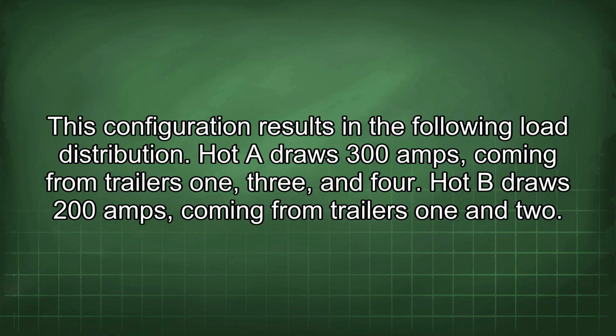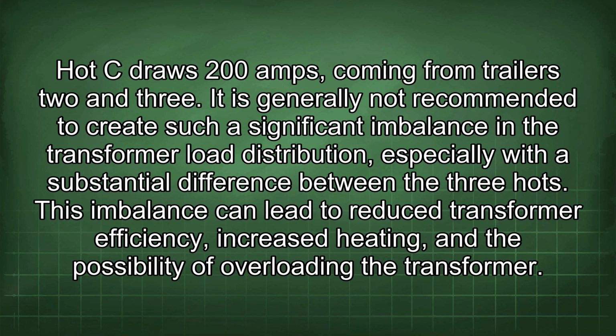This configuration results in the following load distribution. Hot A draws 300 amps coming from trailers 1, 3, and 4. Hot B draws 200 amps coming from trailers 1 and 2. Hot C draws 200 amps coming from trailers 2 and 3. It is generally not recommended to create such a significant imbalance in the transformer load distribution, especially with a substantial difference between the 3 hots. This imbalance can lead to reduced transformer efficiency, increased heating, and the possibility of overloading the transformer.